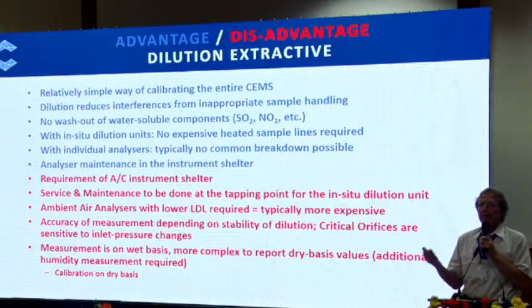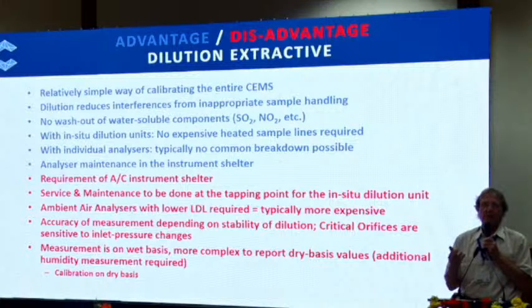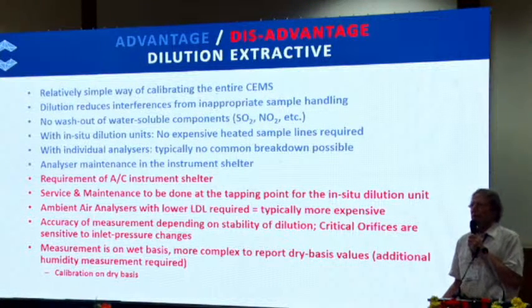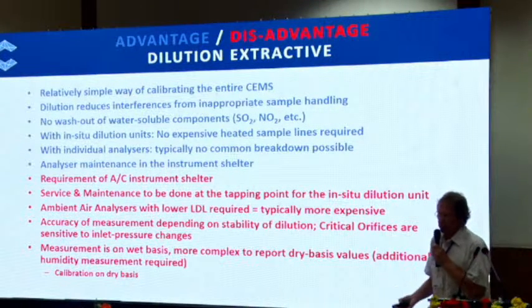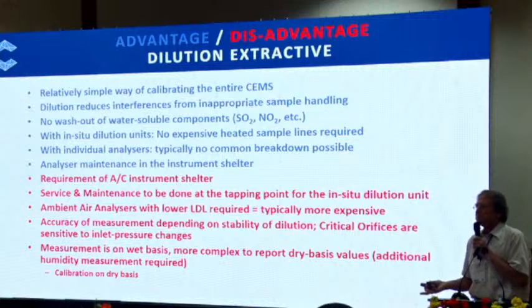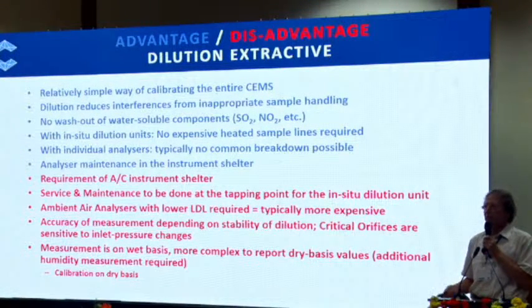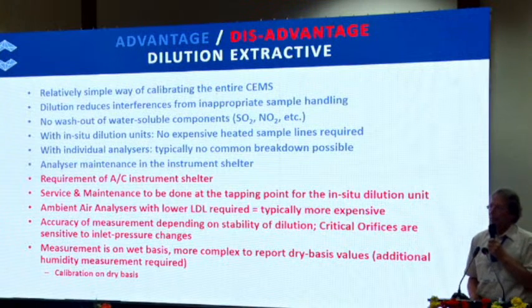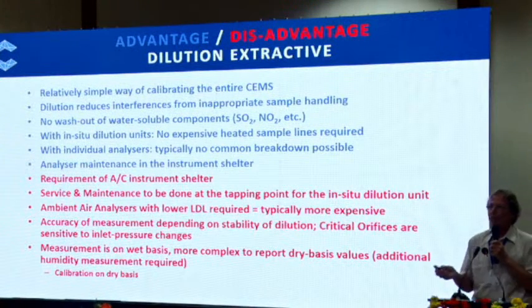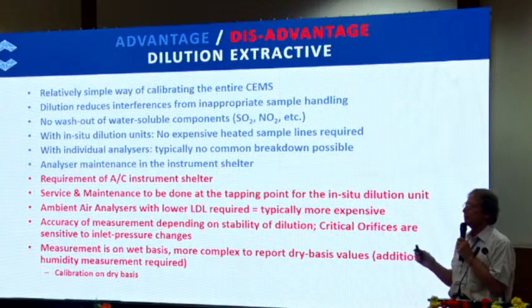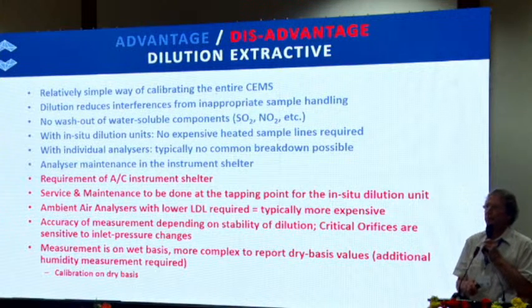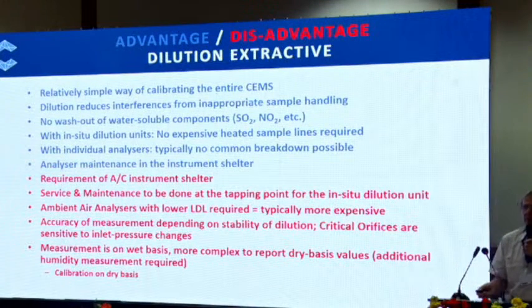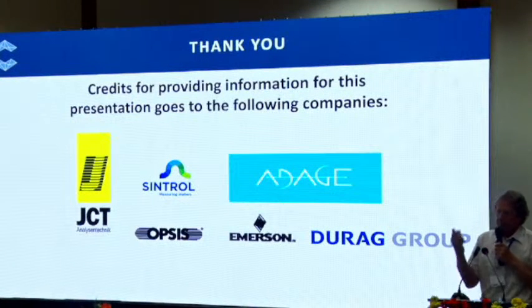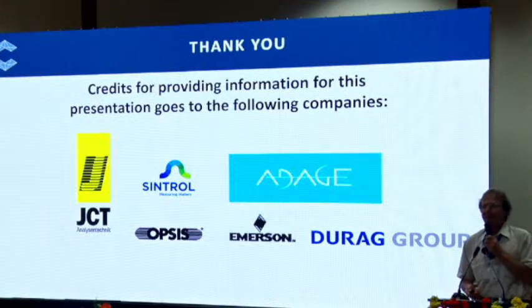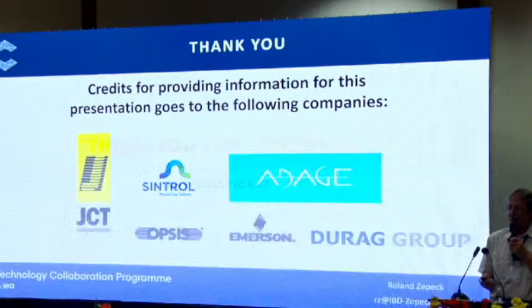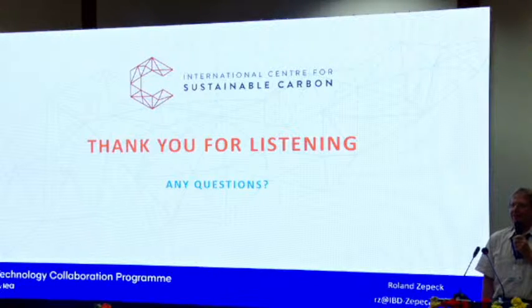And last but not least, like with in situ analyzers, I measure on wet basis because I leave the water in it. I just dilute it so that the diluted sample gas reaches a dew point of approximately 2, 3 centigrade, maybe 4 centigrade. So I need to have my humidity measurement, and I have to be clear that when I calibrate, my calibration gas does not include any humidity, so my calibration is on dry basis, whereas my measurement is on wet basis. These were the guys from whom I stole a couple of the slides, or which helped me creating that. Thanks, that was it. Thanks for listening.